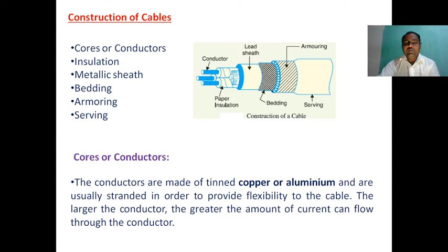The aluminum or copper conductor carries the electrical current. Aluminum conductors are usually used for medium voltage distribution networks requiring long distance and extensive cabling. Copper cables are used for short links in substations and industrial installations where smaller cables with higher power transmitting properties are required. So in cables we use copper or aluminum as the conductor, and depending upon the application we choose the conducting material.